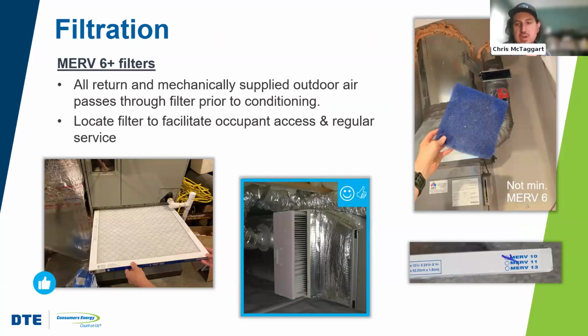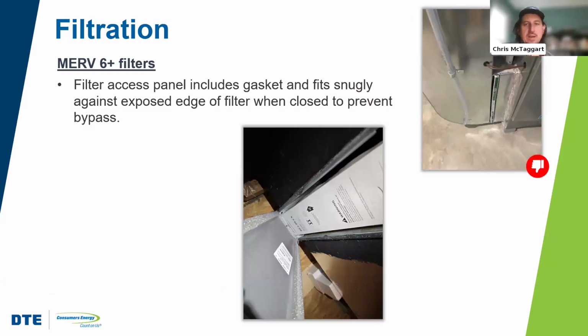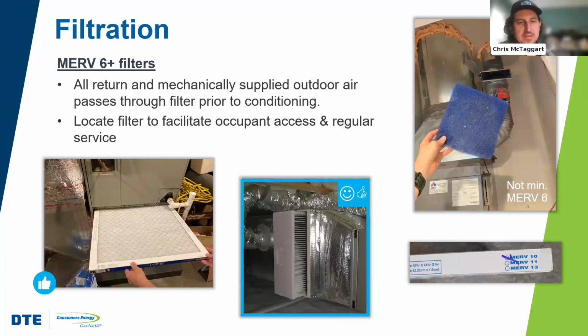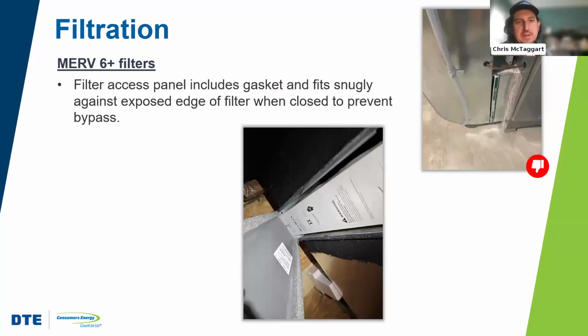System filtration. So our heating and cooling systems need to have at least MERV 6 filters. These are better quality filters, basically, that can help to ensure that ultimately the system is being protected, our air handler is being protected from dust and debris coming in that might foul the blower motor over time, but it also helps to control some degree of dust and allergens in the home for the occupant. So this is something we see people maybe have a construction grade filter in during construction, and then they forget to change it out with a MERV 6. Definitely got to make sure that it happens for the rater to inspect at final.